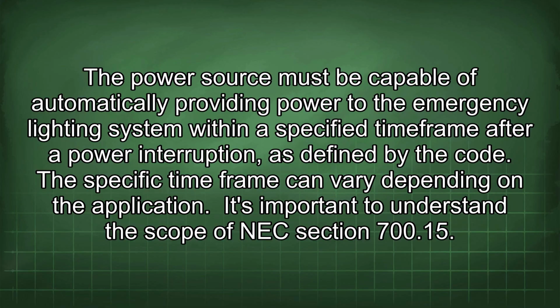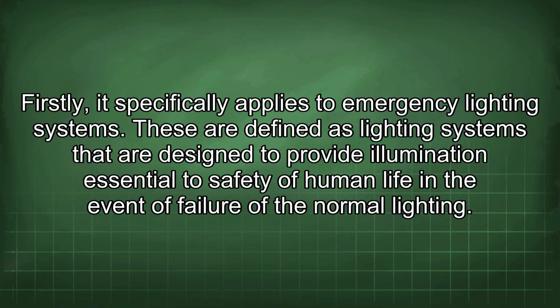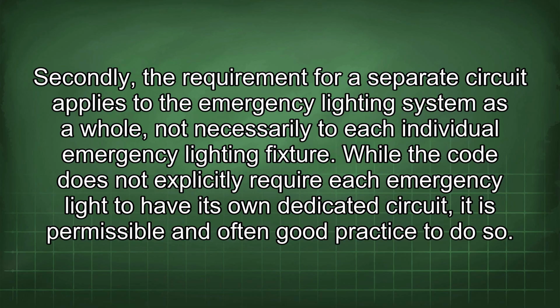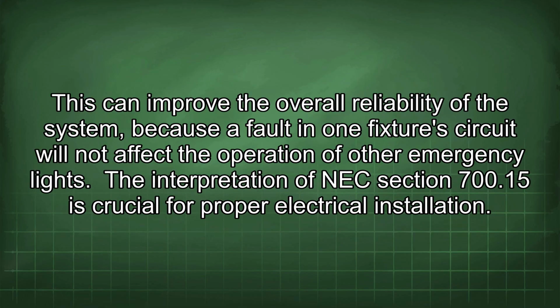It's important to understand the scope of NEC Section 700.15. Firstly, it specifically applies to emergency lighting systems. These are defined as lighting systems that are designed to provide illumination essential to safety of human life in the event of failure of the normal lighting. Secondly, the requirement for a separate circuit applies to the emergency lighting system as a whole, not necessarily to each individual emergency lighting fixture. While the code does not explicitly require each emergency light to have its own dedicated circuit, it is permissible and often good practice to do so. This can improve the overall reliability of the system, because a fault in one fixture's circuit will not affect the operation of other emergency lights.